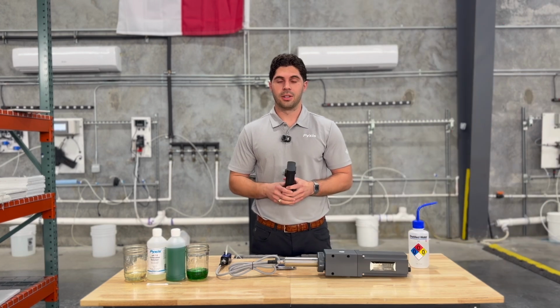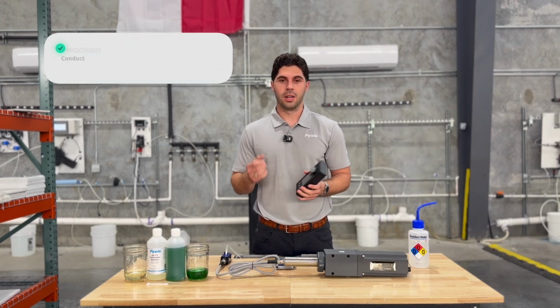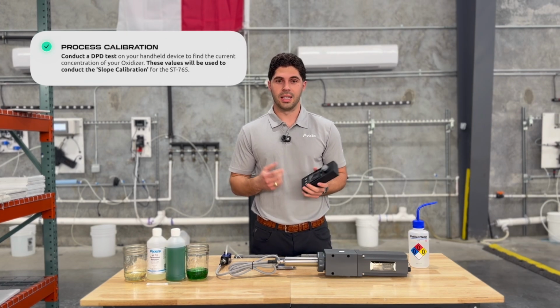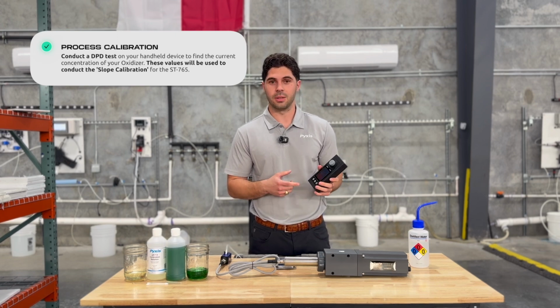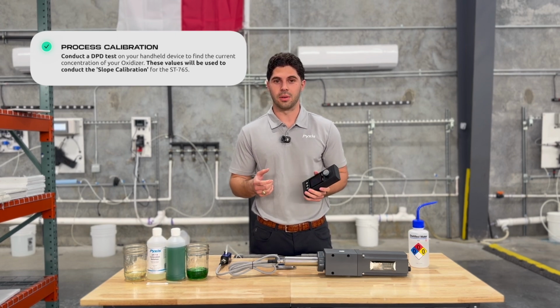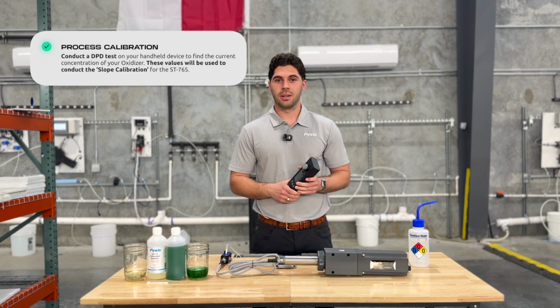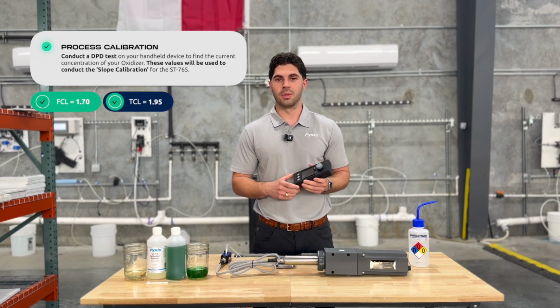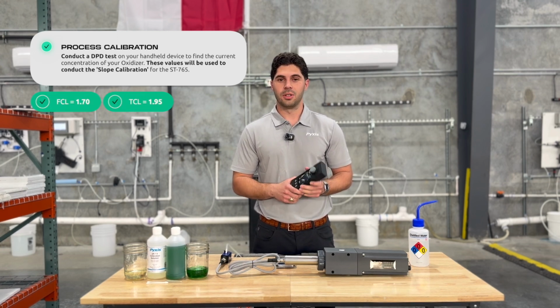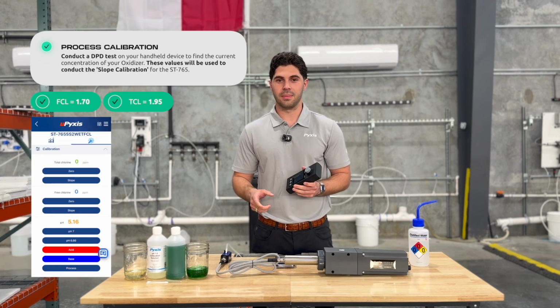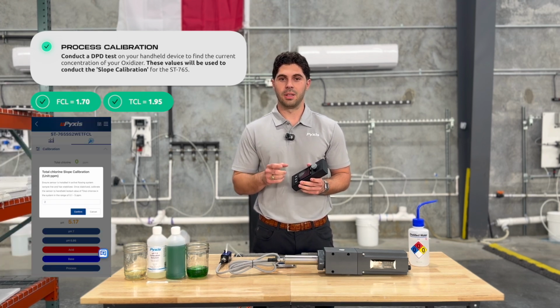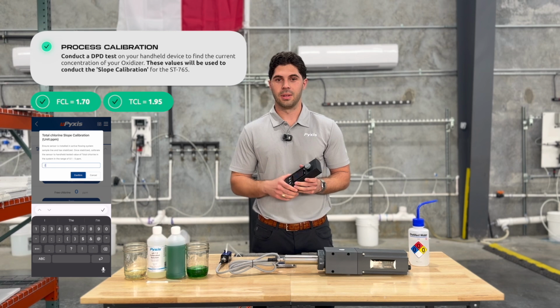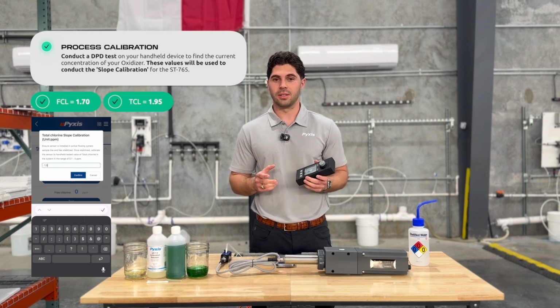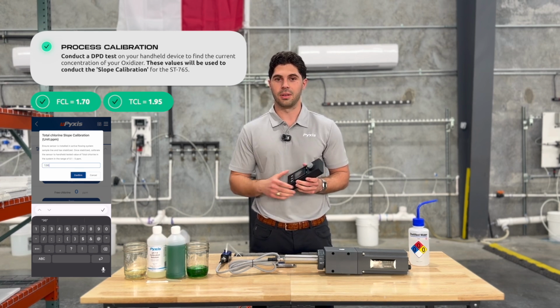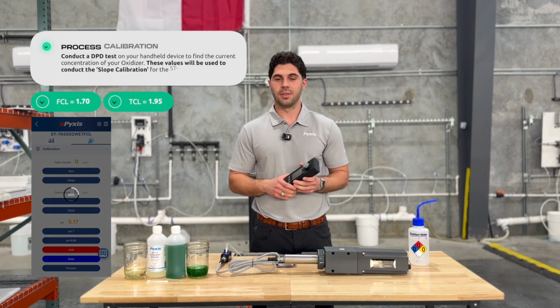For the slope calibration, you want to collect a grab sample and use an offline verification device. In this case, we're using the SP200 OXIPacket to test for free and total chlorine. We found that free chlorine is 1.7 and our total chlorine was 1.95. Once you know this, you're going to head back over to the app, hit slope cal, type in the appropriate number, and hit confirm. In this case, since we have two oxidizers, we're going to repeat the process for both. Once you've done that, you've calibrated your sensor.